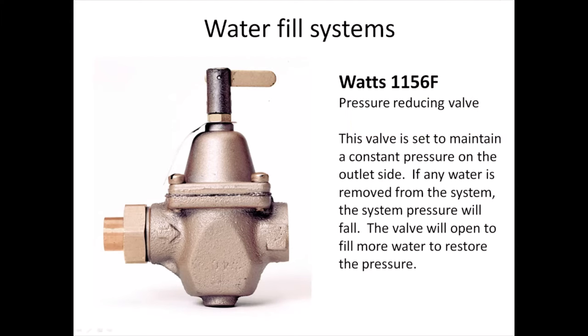Typically, household pressure in the pipes is going to be somewhere in the 50 to 60 PSI neighborhood. The pressure in your boiler system is going to be quite a bit less than that, so there needs to be some way to reduce the pressure from normal domestic water pressure down to boiler water pressure. The pressure reducing valve has that job. The valve is set to maintain a constant pressure on its outlet side. If any water is removed from the system, the system pressure falls, and the valve responds by opening a little bit to fill more water and restore that pressure. When pressure is back to the set point, it stops filling.